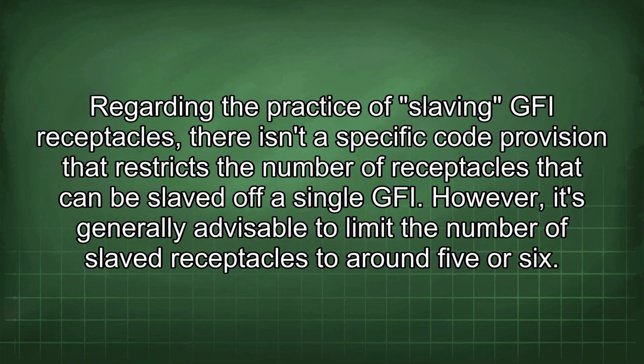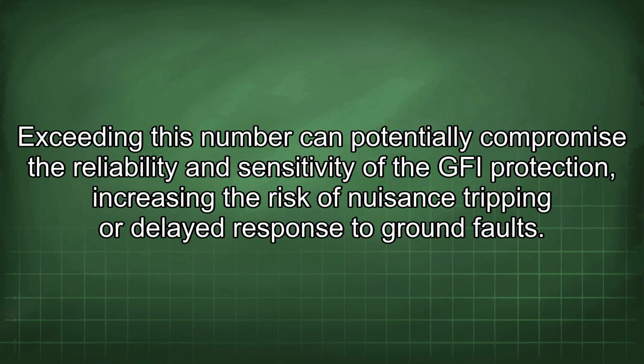Regarding the practice of slaving GFI receptacles, there isn't a specific code provision that restricts the number of receptacles that can be slaved off a single GFI. However, it's generally advisable to limit the number of slaved receptacles to around 5 or 6. Exceeding this number can potentially compromise the reliability and sensitivity of the GFI protection, increasing the risk of nuisance tripping or delayed response to ground faults.